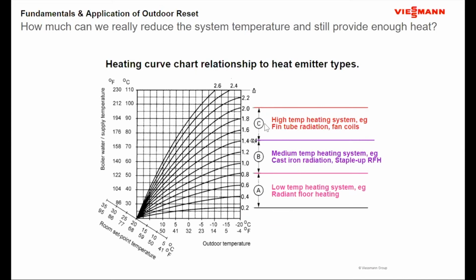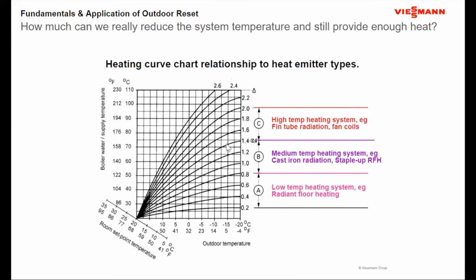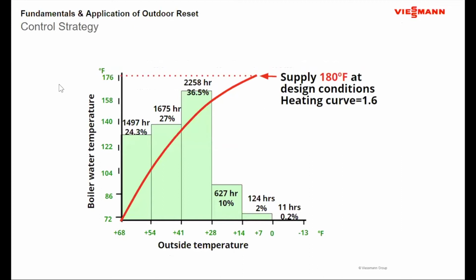Ideally, somebody has done a design where you know the outdoor conditions and you know the design water temperature, because if I'm designing off of here, it really becomes an educated guess of where I need to be. But if I can say I'm designing for a 5 degrees Fahrenheit day with 158-degree water, here's my 5-degree temperature, here's 158, it's pretty close to a 1.4. I know that 1.4 curve is the best relationship for my building and my heat emitters throughout that building. But it really becomes a key point in setting it up. And then through this control strategy, we can set the water temperature and then we start to modulate that water temperature.